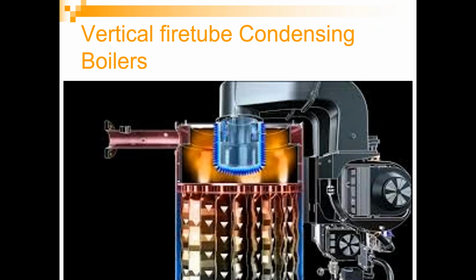There have been a lot of boilers coming out on the market, and there's been a run for Firetube boilers, and people have turned them upside down, and a lot of manufacturers have started releasing what's called a vertical condensing Firetube type boiler. There's been a rash of failures in this type of boiler as people have rushed this type of product to market.